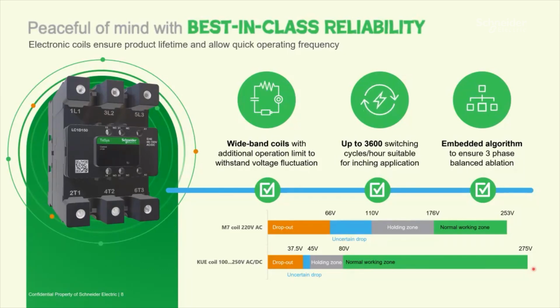Similarly, the holding zone for the existing contactor is 110 to 176 volt, whereas for the new contactor it will be 45 volt to 80 volt. So we can now definitely say that this contactor will work even if there is a lot of fluctuation in voltages. From 45 to 275 volt, this contactor will hold on to the contacts. And for the existing contactor, if there is a voltage drop, let us say somewhere between 66 to 110 volt, you are not certain whether the contactor will hold or drop.